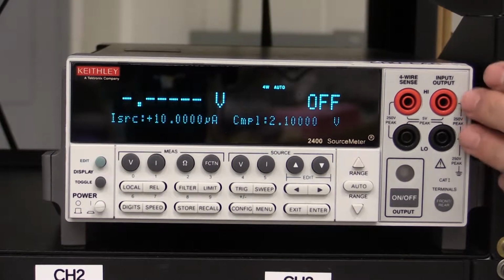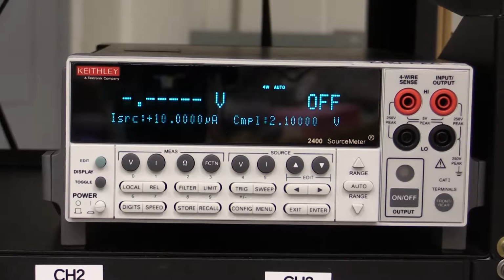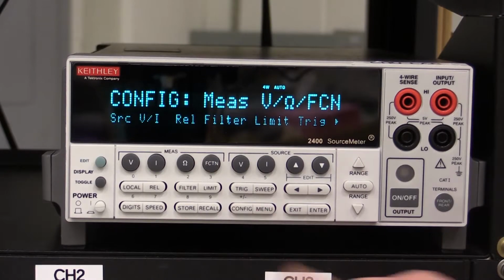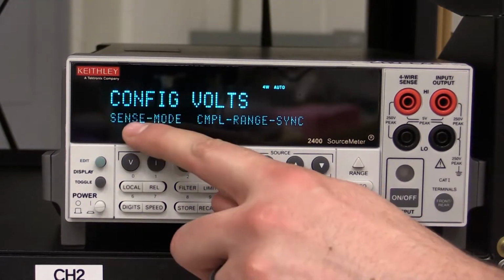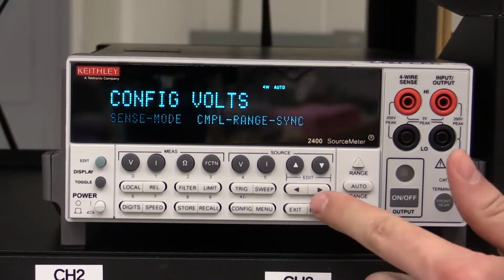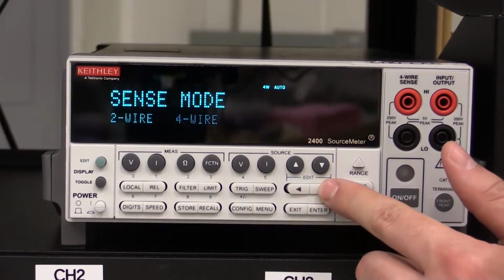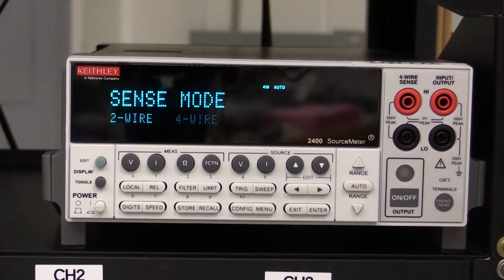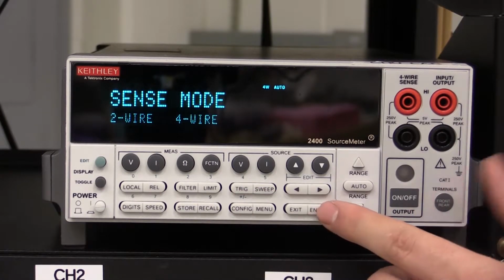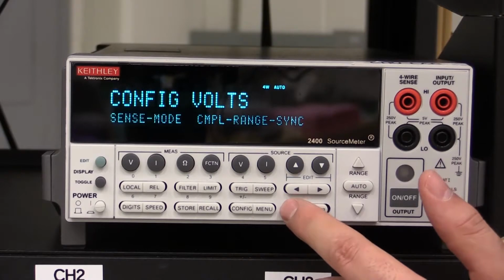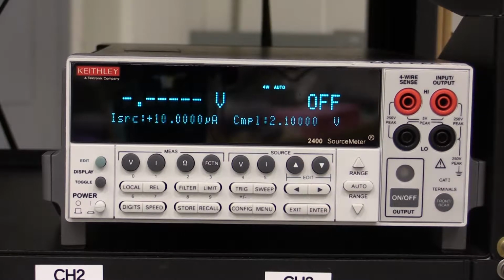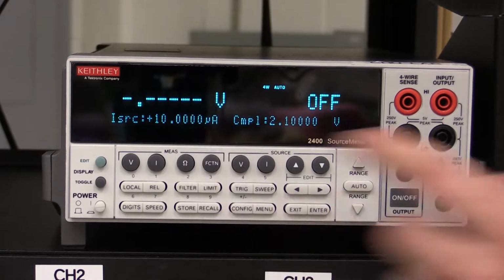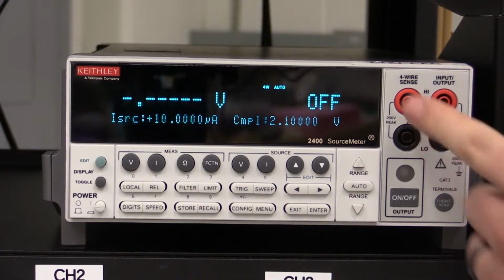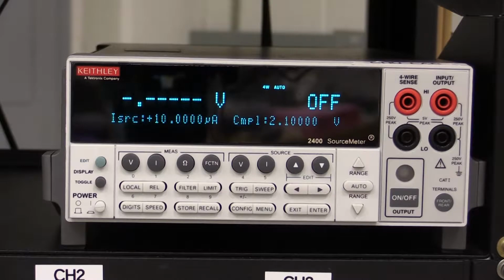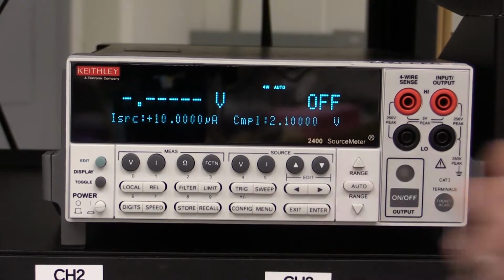If you would like to source and sense on a different part of the circuit, you can put it into what's called four-wire sense. To do that, you hit the config button, measure V, and you'll see this sense mode flashing as an option. You can select that and switch between two wire and four wire sense. You can see I already had it set up in four wire sense. So we'll select that and exit out of this menu. So right now, the instrument is configured to source current through these two terminals and sense voltage through these two terminals. You know it's in four wire mode because you see this little four wire icon right there.